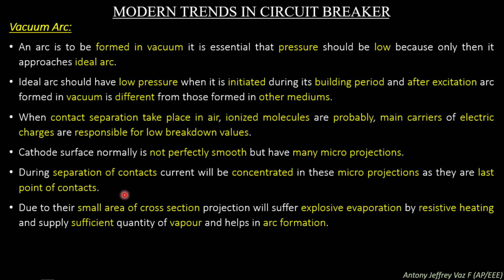Due to the small area of cross section, the projections will suffer explosive evaporation by resistive heating and supply a sufficient quantity of vapor, which helps in arc formation. So due to the small cross section, the projections undergo explosive evaporation through resistive heating, and this resistive heating explosively evaporates the metal. This metal vapor will help in arc formation in vacuum.